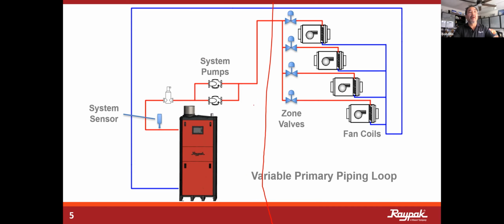Nobody's really looked at the coils. They put the stainless steel fire tube in, and of course nobody's really complaining, because that boiler is going to ramp up and down, and the pumps are going to ride on their curve. But as these valves begin to close, our pathway back to the boiler in order to maintain minimum flow is definitely reduced. If we don't have enough three-way valves in the system, and if the boiler doesn't get its minimum flow and there's a call for heat, it will begin to stress the heater, especially if the heater can't monitor its own flow rate, GPMs.